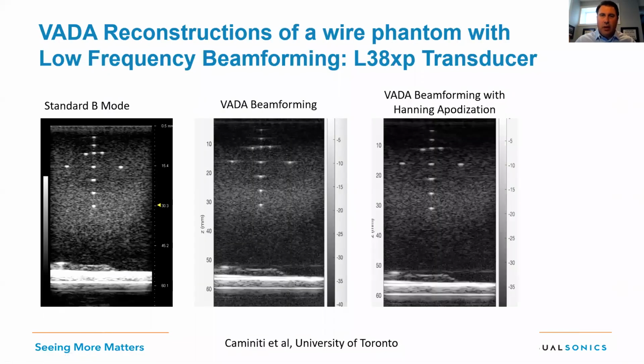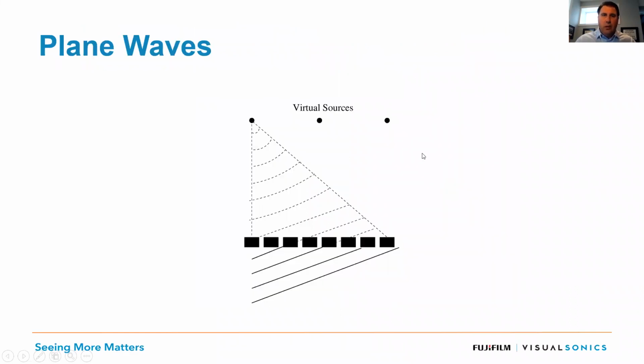I should point out, apologize, just come back. This is actually done with that L38 XP transducer, so you get a sense of the depth in the phantom. We're almost 5 to 6 centimeters in this case, or 60 millimeters deep. So much deeper than we're used to with our higher frequency transducers. So this is really nice to see as well. So conventional beamforming, that's fine. That's fairly well known, and those last images really validated what we are seeing on the system and the VADA interface itself. But what about plane waves?